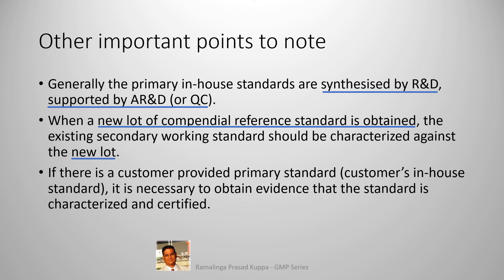If there is a customer-provided primary standard — that is, the customer's in-house standard — it is necessary to obtain evidence that the standard is characterized and certified. The customer who provides the primary standard should provide a declaration that it is characterized and certified to its claimed structure, purity, and potency.